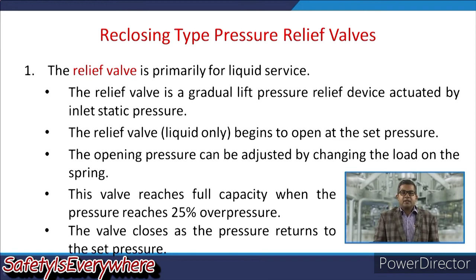The relief valve begins to operate at set pressure. The definition of set pressure we have already discussed in a previous module. The opening pressure can be adjusted by changing the load on the spring. This valve reaches the full capacity when the pressure reaches 25% overpressure if it is set at 25%. The valve closes as the pressure returns to the set pressure.